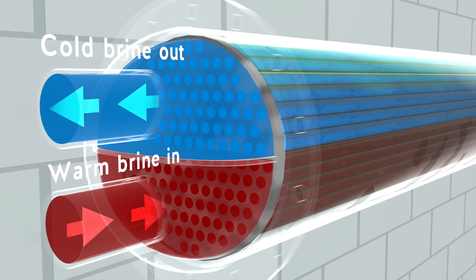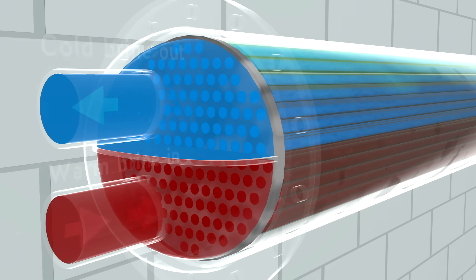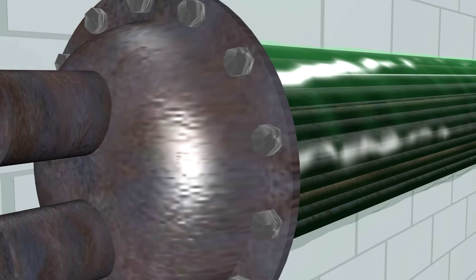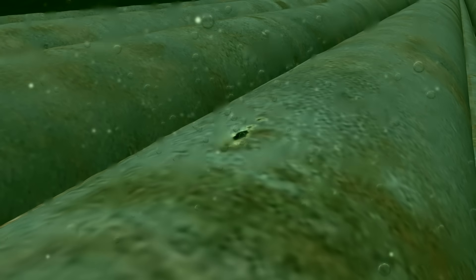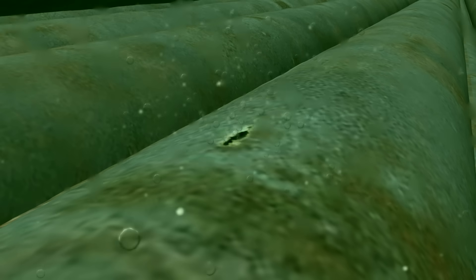It is critical that the brine and ammonia never mix. Due to corrosion over time, a pinhole developed in one of the curling rink's chiller tubes, allowing ammonia to leak and mix with the brine. This leak was not repaired during the 2017 summer seasonal shutdown.